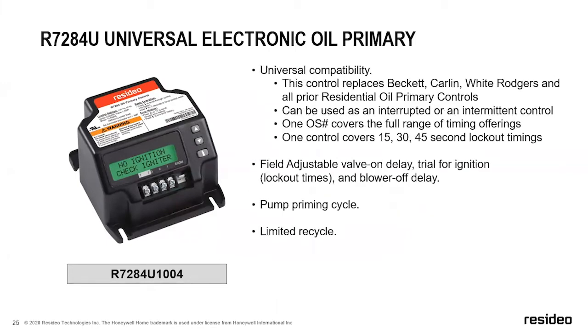The other thing is it's universal compatibility. So it replaces Beckett, Carlin, White Rogers, and all other prior residential oil primary controls that you could find on the universal replacement on the box, and furthermore in our installation manuals. You can use it as either an interrupted or an intermittent control. So you can have the device continue to spark while you've already proven flame, or be intermittent. One part number covers the full range of timing offerings. So what I mean by that, you can have 15, 30, and 45-second trial for ignitions.